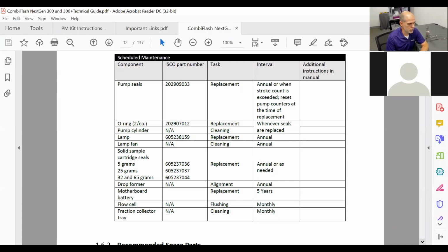Flow cell. Flow cell is the component. There's 2 fiber optic rods inside of it that make a gap. Your solvent sample is moving through that gap and the light shines through there. That's how the machine works in a nutshell. So the flow cell needs to stay clean. These are quartz rods. They look like glass, okay? They need to stay clear. They need to be able to pass light through them. So we recommend flushings, all right? We recommend every now and then you take it out and inspect it. I'll show you how to do that today.